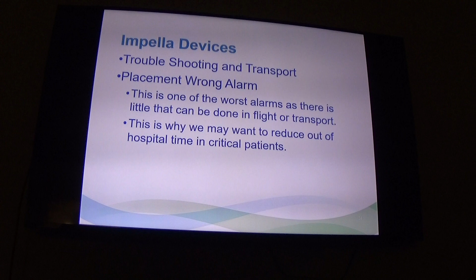So the first one where you have a problem is, can anyone tell me where this would be? You have what looks more like an arterial waveform, and again, you know that the motor current is flat. Motor current asystole means the device is in neutral, it's not working. So it's dislodged. Yeah, it's in the aorta. So this is actually a really bad position, because the device may be completely out, and once you're in this position, you may not even be able to advance it, because you may have to cross the aortic valve. We don't do that.